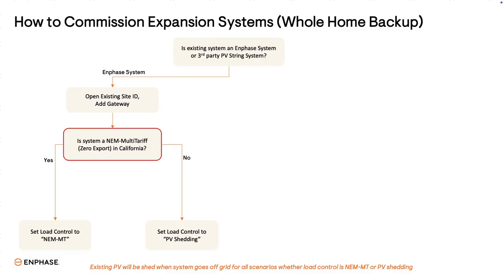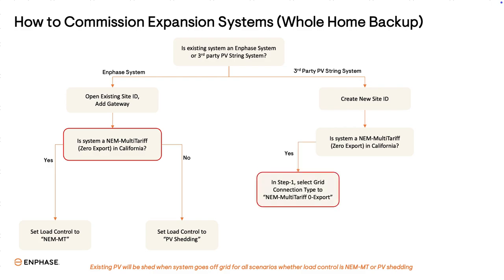Going back to the top of the decision tree: if the system is a third-party PV string system, you will create a new Site ID in the installer app. Then determine if it's a NEM multi-tariff system in California. If yes, set the grid connection type to NEM multi-tariff zero export in step 1, then set load control to NEM MT. If the system is outside California and it's not a NEM multi-tariff system, set the load control to PV shedding. Please note, existing PV will be shed when the system goes off-grid for all scenarios, whether load control is set to NEM MT or PV shedding. The difference is for NEM MT: in addition to PV being shed, the new system is zero export and the existing PV doesn't charge batteries.